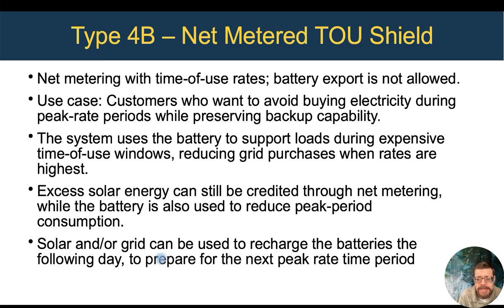Some places are still doing net metering, but with time of use rates, they also have a peak time in the evening. And here's where we want to do a combo and say, we're going to draw our own local loads from the battery during that peak rate time, and then we'll wait for solar to charge it up, or maybe we'll use grid power to recharge it if that's allowed. Some grids don't want you using grid power to charge the batteries, which is confusing to me because they think it's fine to charge an EV or your computer with grid power, but they don't want your solar system batteries charged with grid power.